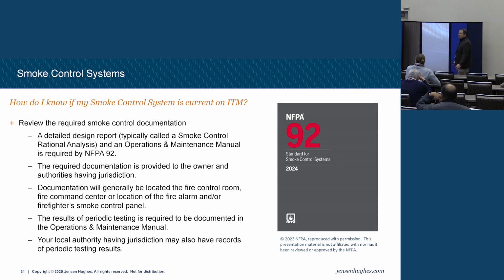Okay, so how do I know if my system is current? All that basically says there's supposed to be documentation. There's supposed to be records of every test. There's supposed to be that original rational design document. All that is supposed to be maintained either in your fire command center or your security office, something of that sort. That's basically what all of that slide says. Your local authority having jurisdiction probably maintains records on it too. There are now automated cloud-based solutions that will do all this for you.